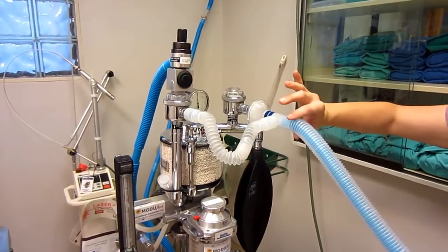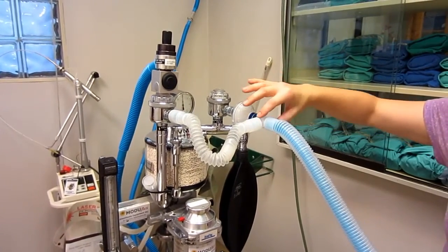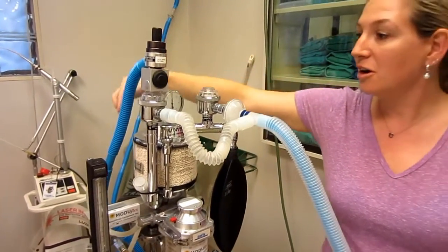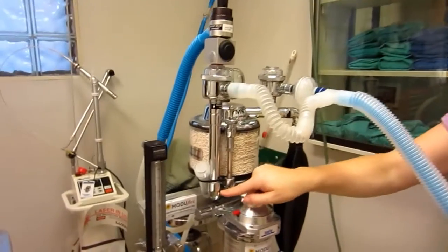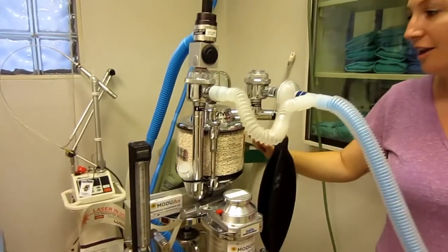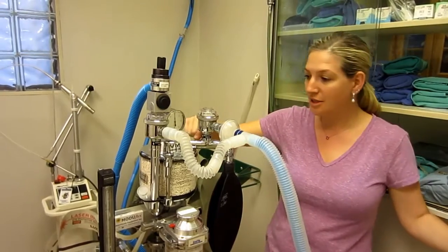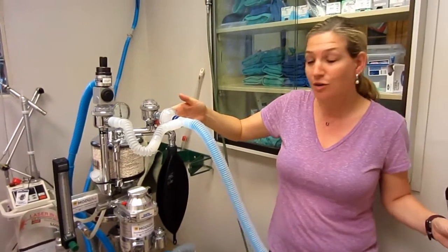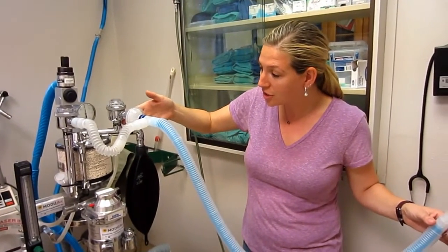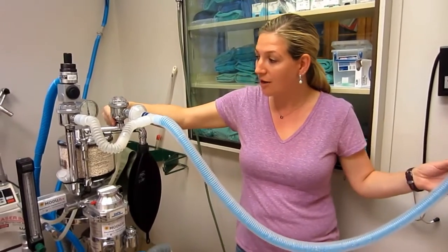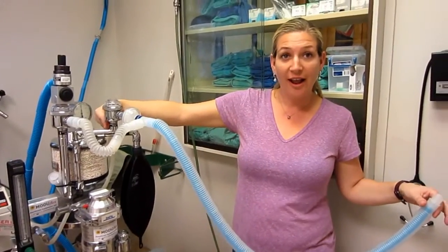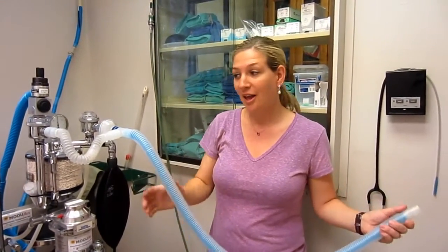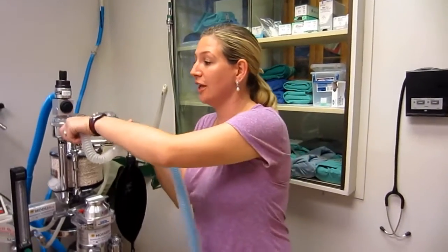It's going to be carbon dioxide, isoflurane gas, as well as a little O2 comes into the exhalation valve. Some of it goes out our exhaust. The other portion goes through our CO2 absorbent canister, and then we come out into our inhalation valve again and get mixed with our fresh O2 and fresh isoflurane. And to be clear, what comes out here is oxygen and isoflurane to be reused, and it all goes back in again. And so that's one rebreathing circuit.